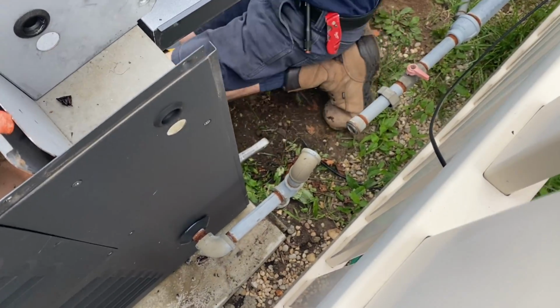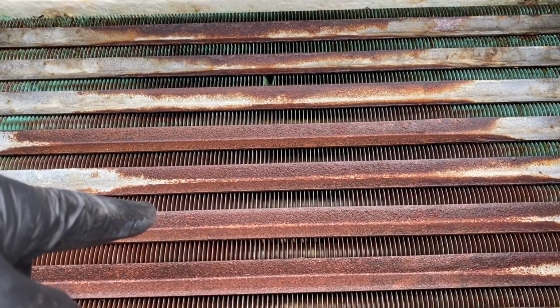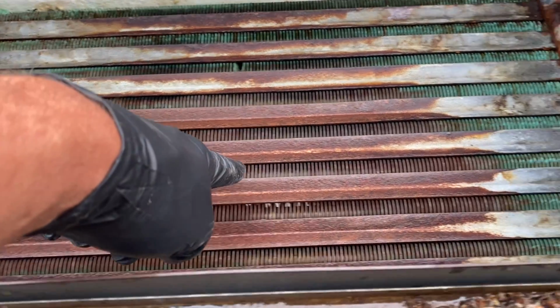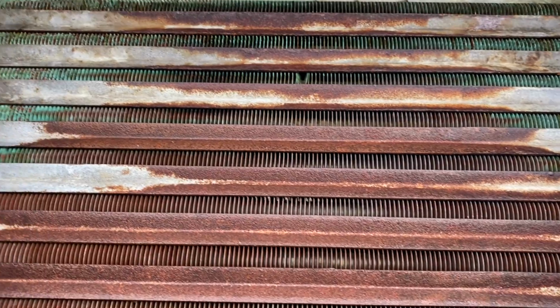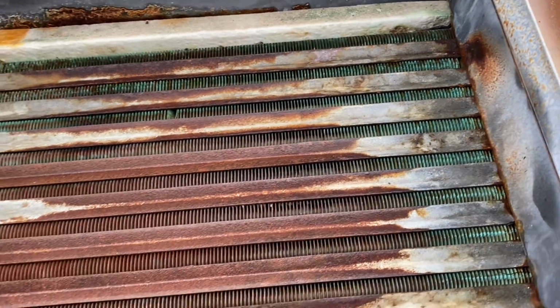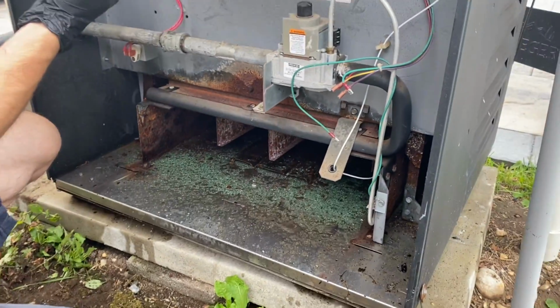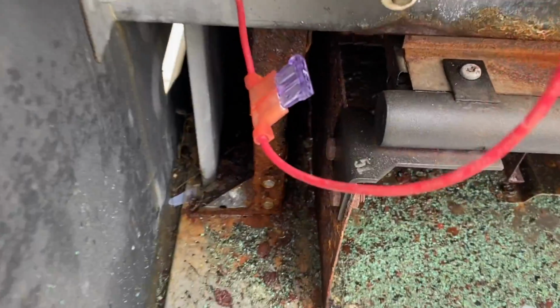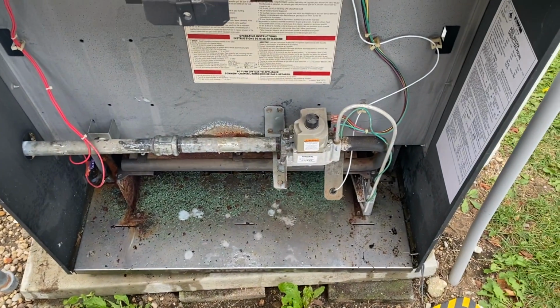Daniel is working on re-putting in the gas. And hopefully, I could see down in certain parts of it, so that's good. You guys can't see it, but I see light down there. So hopefully we cleaned up the rollout condition. And as long as it's running safely, I have no problem with that, but we shall see. That's all the stuff that came out of it. We shall see. All right, so for testing purposes, just putting a fuse in there. I could have put a jumper there as well. Just trying to purge the air out.